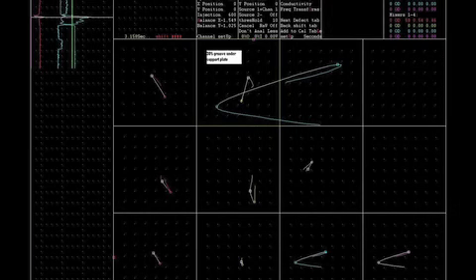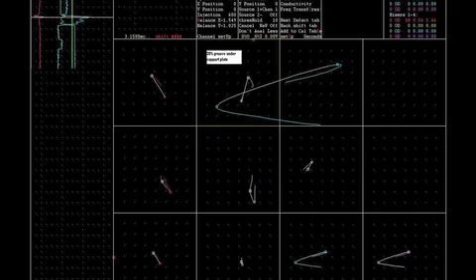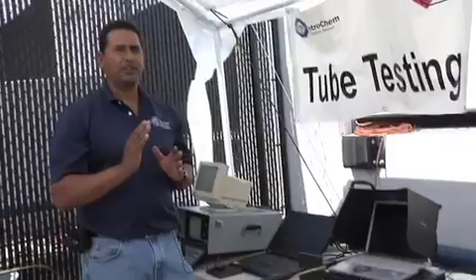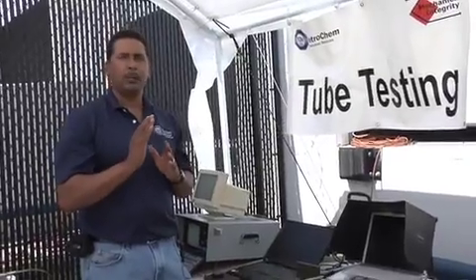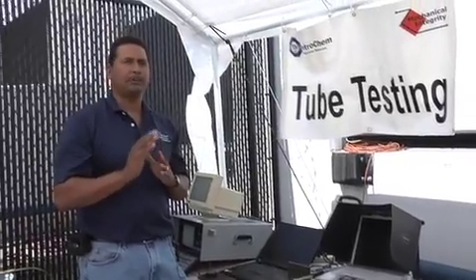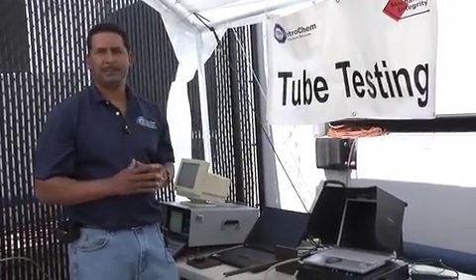I'm still reading that close to 20%. So despite the amplitude difference, at times you would get a slight phase shift, but the measurement is within 2%.